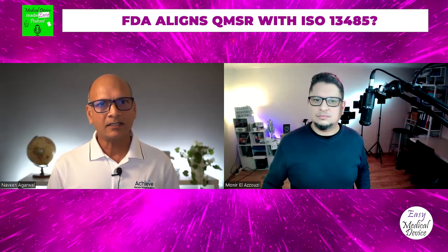Basically, what the FDA has done is incorporated the entire ISO 13485 2016 revision by way of reference. So what they are saying is that by way of reference, we are including the entire ISO 13485 2016 version as part of our official quality management system regulation. And what that basically does is you have to comply with all the clauses, plus some minor differences in definitions, because FDA also needs to make sure we are complying with the food, drug, and cosmetic regulation - that's the law in the United States, and they don't want to create confusion or discrepancy with the law.